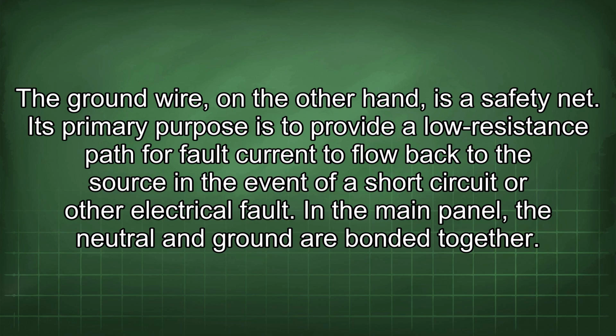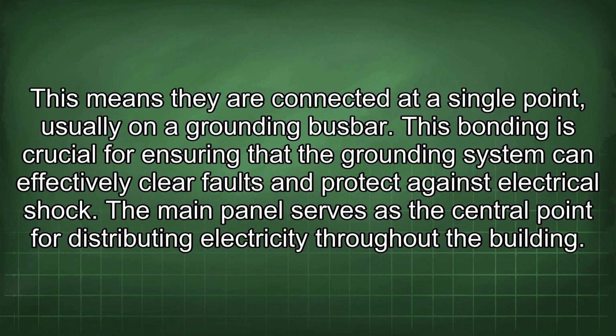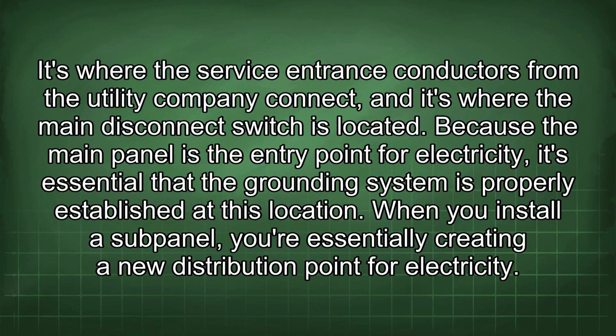In the main panel, the neutral and ground are bonded together. This means they are connected at a single point, usually on a grounding bus bar. This bonding is crucial for ensuring that the grounding system can effectively clear faults and protect against electrical shock. The main panel serves as the central point for distributing electricity throughout the building. It's where the service entrance conductors from the utility company connect, and it's where the main disconnect switch is located. Because the main panel is the entry point for electricity, it's essential that the grounding system is properly established at this location.